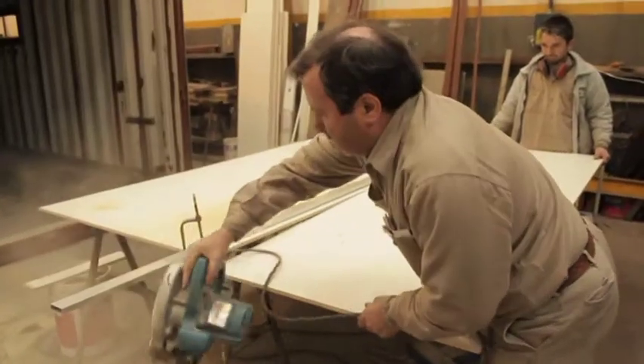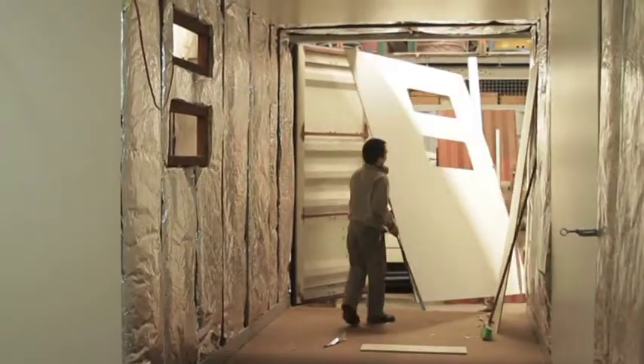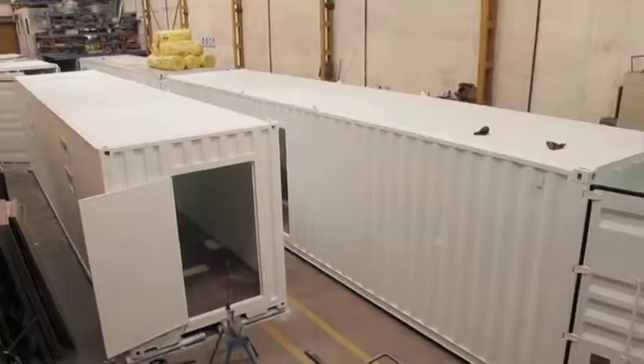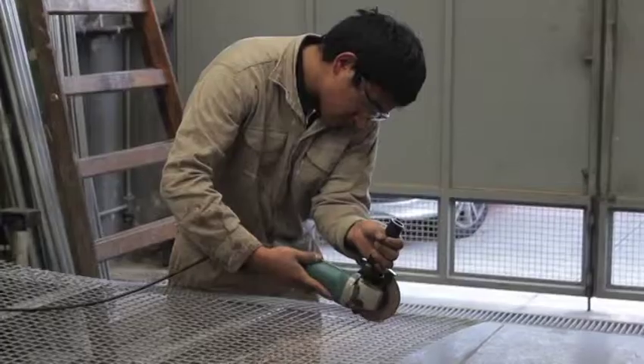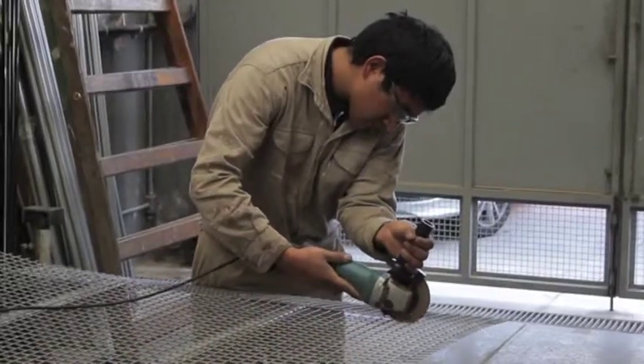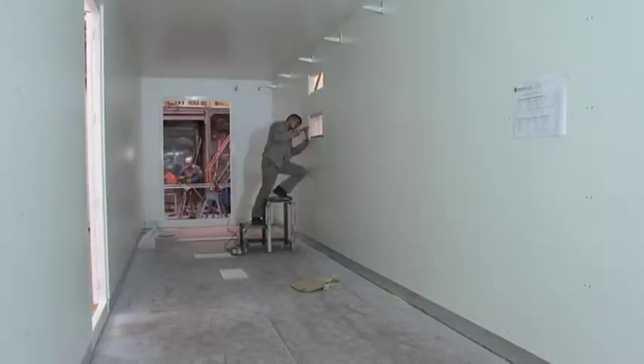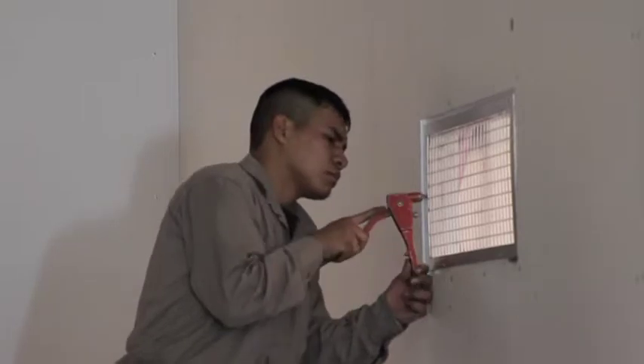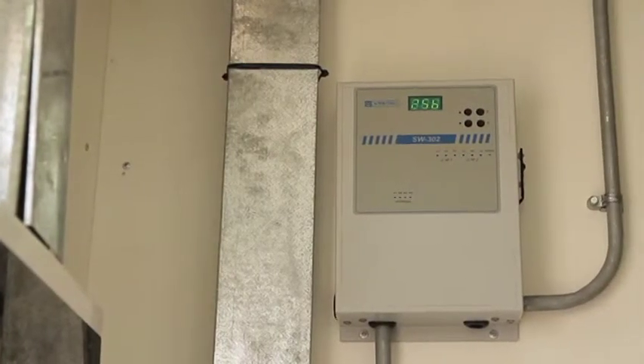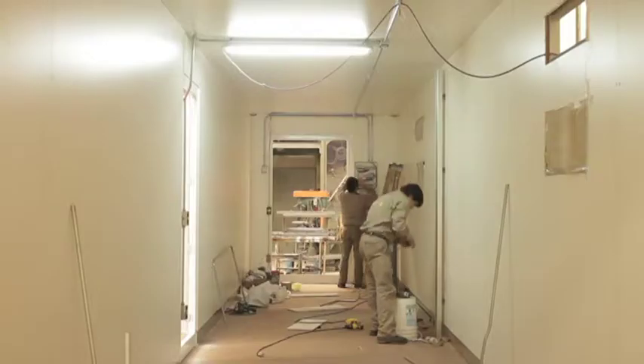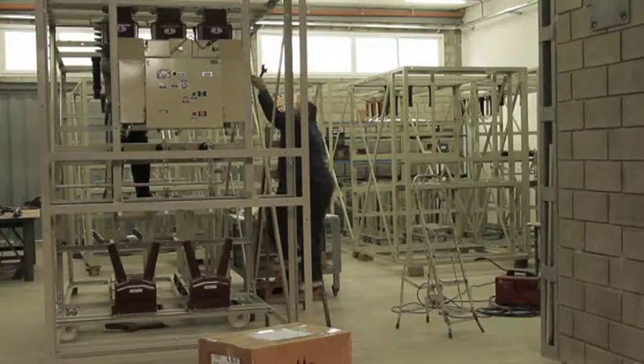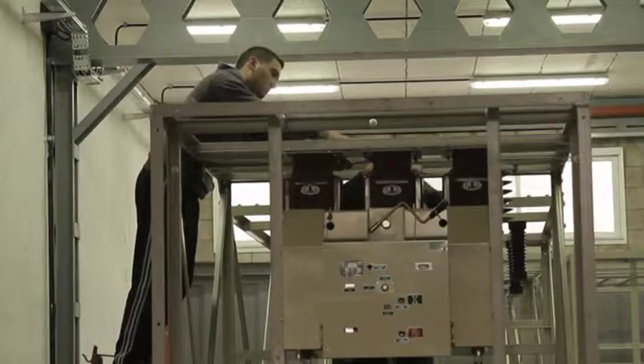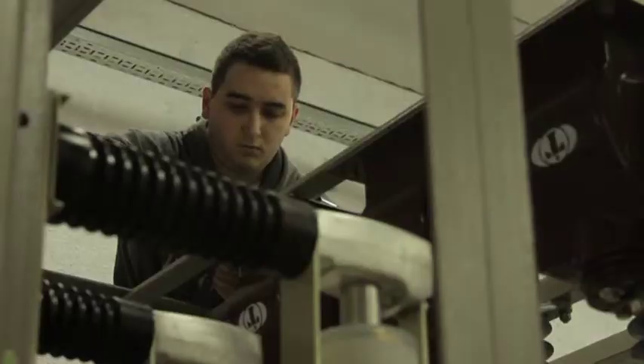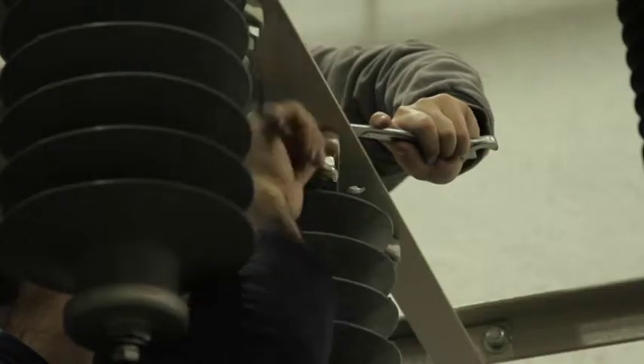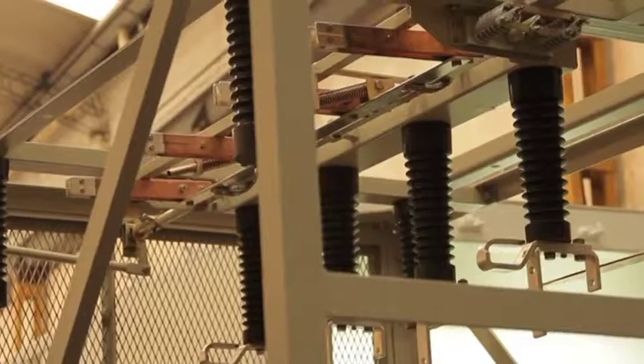The containers were conveniently adapted as mobile electrical rooms, adding access doors, complete thermal insulation, auxiliary voltage wiring, internal lighting, and a double air conditioning system, with one operating unit and one backup unit, each of them capable of evacuating the heat generated by equipment housed in the container, plus heat influx from the surroundings, even at maximum ambient temperature conditions.